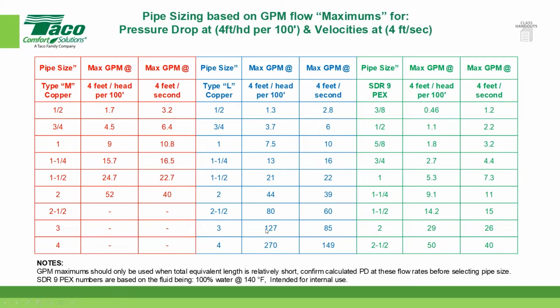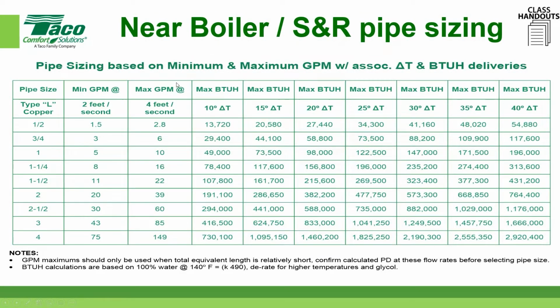This is part of your handouts. Again, look at this one. This is a little different. Notice I didn't give you the ASHRAE number. This is just kind of modern hydronic stuff. But what I wanted to use this for is a quick lookup to say, hey, if I had a piece of 1 inch type L copper, I could keep it at 5 or above and 10 or below. So I like to look at it in here. Anything between 5 and 10, you're in the sweet spot. You're good. You're not going to blow either of those rules, either 4 feet per second or 2 feet per second. You're going to stay right in between those two.